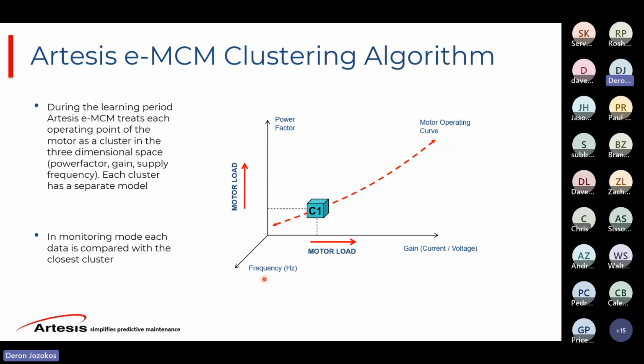So the system now starts custom building all these math models specific to the process. And all these little clusters are a factor of power factor, gain, supply frequency, and a number of other parameters to start now learning what is the normal process for that particular motor. So now when it's in the full monitoring mode in its normal operation, it's comparing apples to apples all the time based on the different load parameters it saw during the learn period.